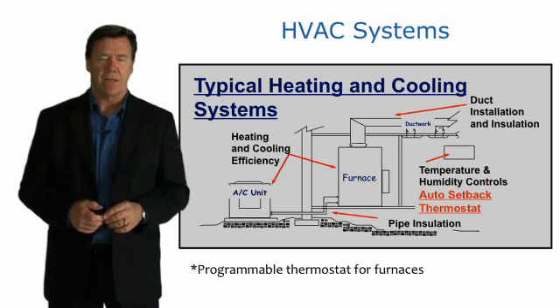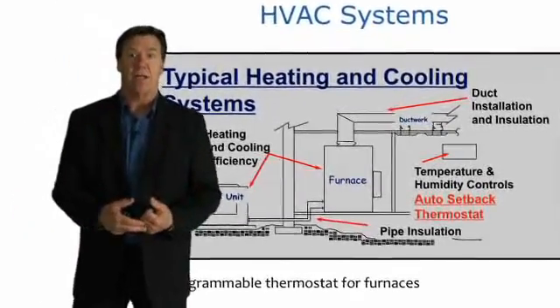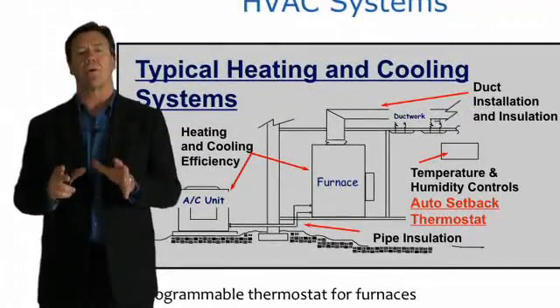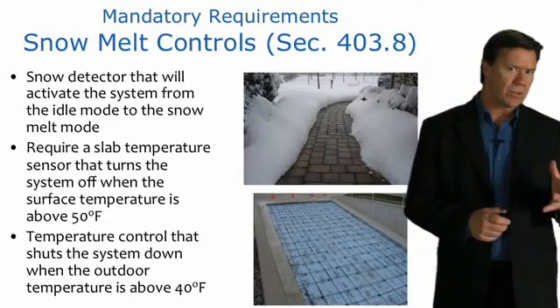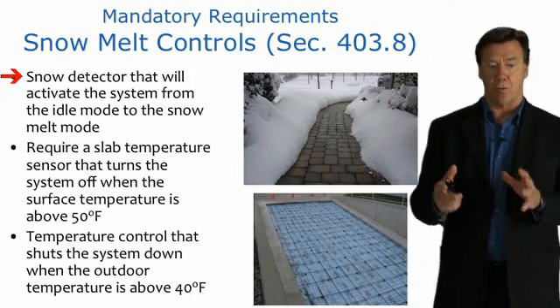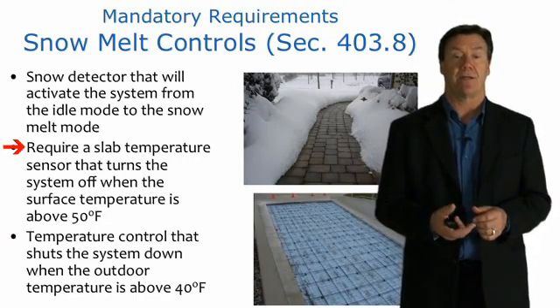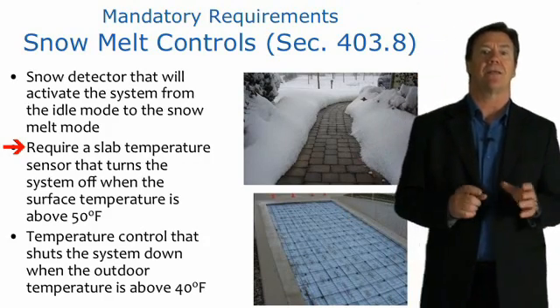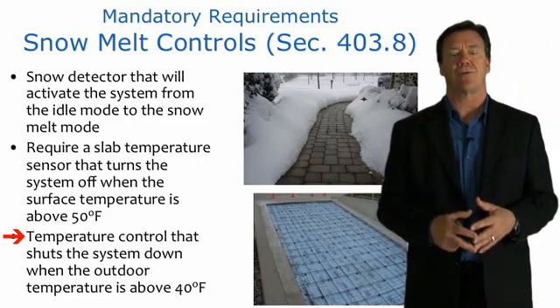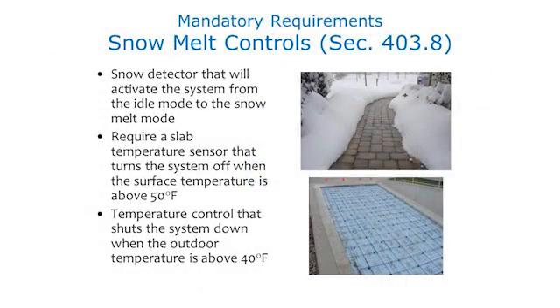We want adequate sizing. Each individual system — distribution system, outdoor system, furnace, and air handler — must have its own setback thermostat. For snow melt controls, we must have a snow detector that activates the system from idle to snow melt mode, a slab temperature sensor that turns the system off when the surface temperature is above 50 degrees, and a control that shuts the system down when the outdoor temperature is above 40 degrees. Nowhere in the Kentucky residential code is a snow melt system required, but if one is provided, these controls are mandatory.